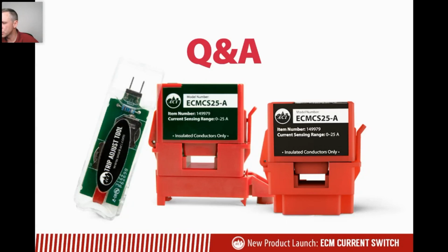Another question is, are there dual set points? And no, there's only one set point. And the question continues, what about integral, where minimum speeds may draw a 1/4 amp, but standby is 0.2 amps. That's where you have to be careful in setting the set point. You can set the set point of this device above 0.2 amps. So you can set it at 0.22 or 0.23 so that it's above the standby but below the minimum speed. So there's not two set points built right in, but you can set it in between that standby and that minimum draw. Other scenarios that we've seen in the past is where people will use two devices and set one at the peak of the standby, and then one at the minimum level.